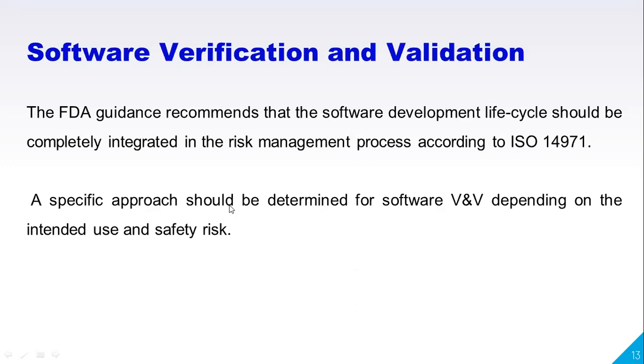It is a part of risk management. See, even a minor bug will change things, so that is a risk. So this comes under the risk management process. A specific approach should be determined for software verification and validation depending upon the intended use and the safety risk.